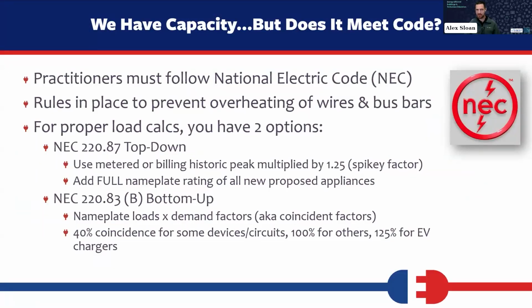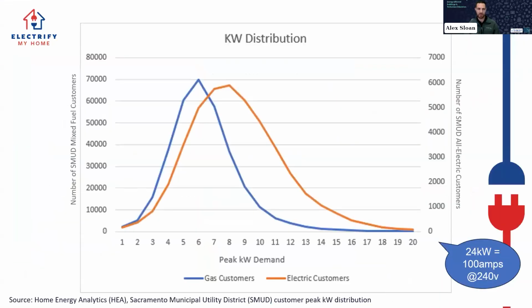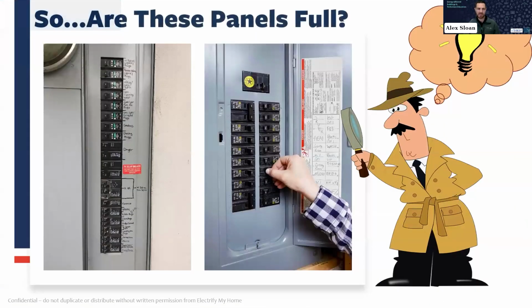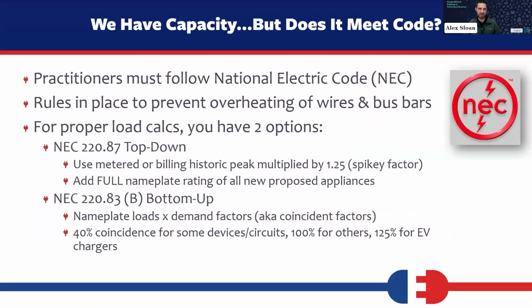So with that said, we have capacity, but does it meet code? When we look back at this chart showing that we almost never reach the peak demand allotted by our panel, we actually have to plan ahead for worst case scenarios, which is why we need to follow the National Electric Code. That's what brings us to the tendency to want to oversize our electrical panels, for safety reasons. The NEC requirements are in place to prevent overheating of the wires and bus bars, and it's really in place for safety.